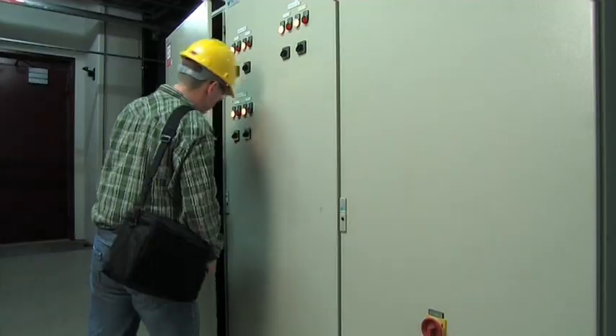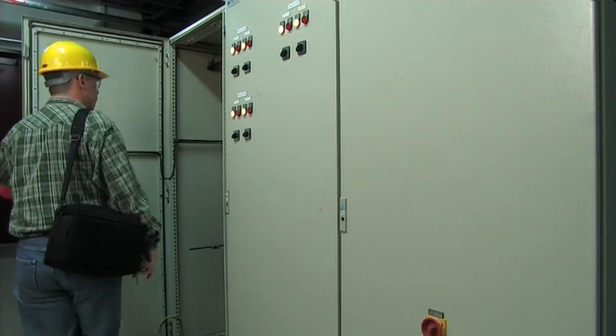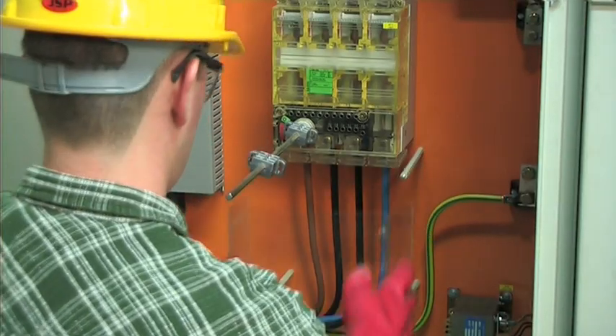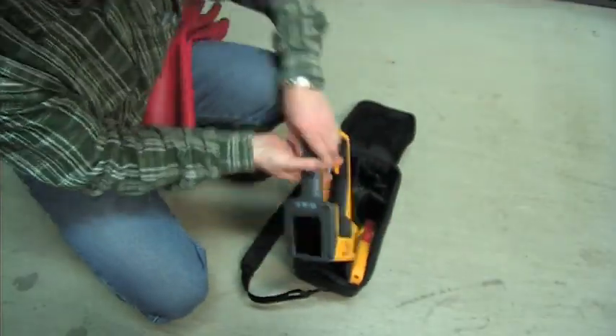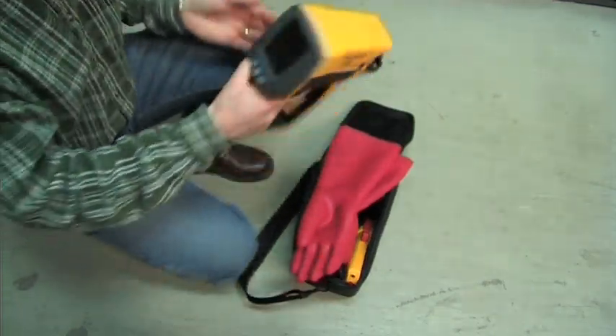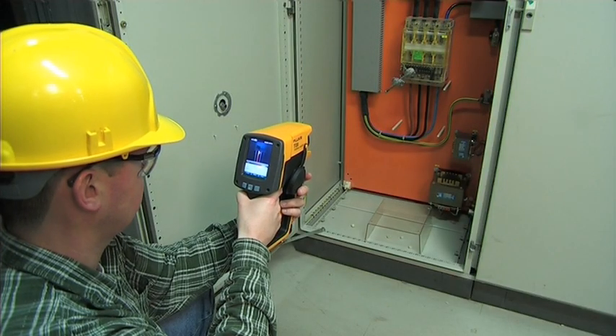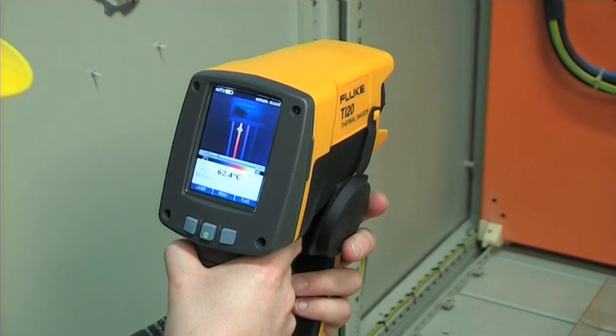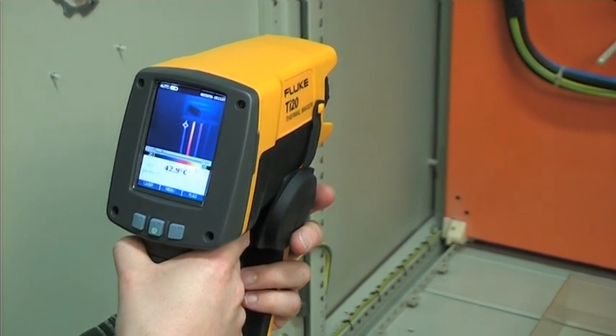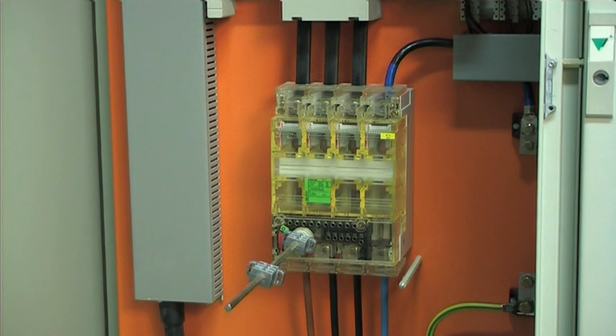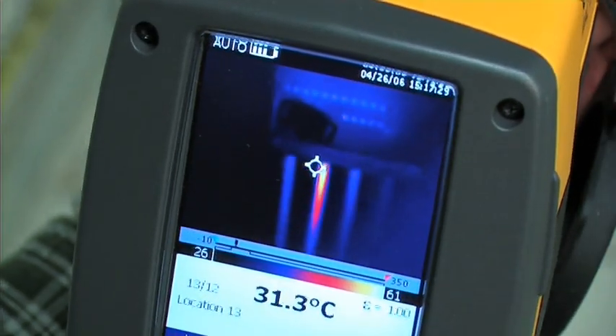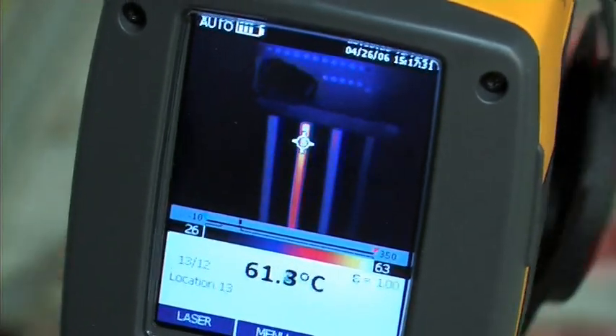There are many ways thermal imaging can help you conduct planned maintenance. We're going to take a closer look at some of the most common ways. Thermal images are powerful aids for identifying power quality related problems in three-phase electrical panels. Even a small temperature difference between phases might indicate an unbalanced or overloaded system, bad wiring, loose connections, or problems with harmonics.